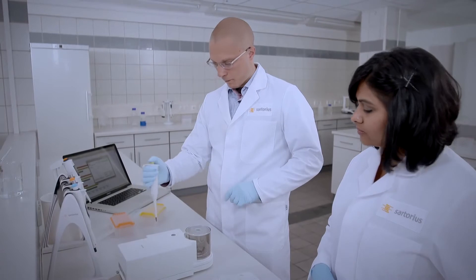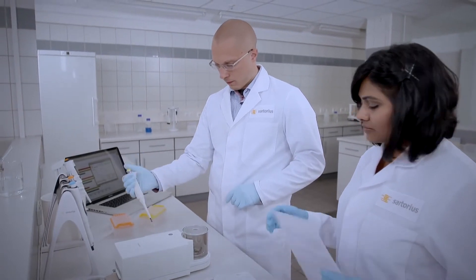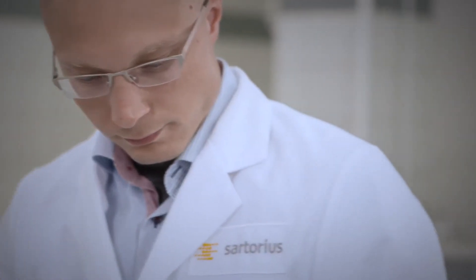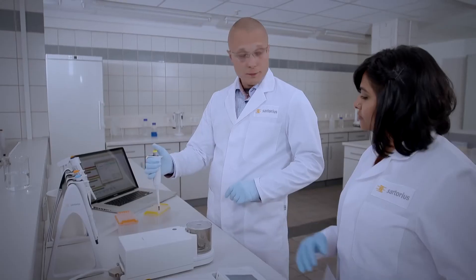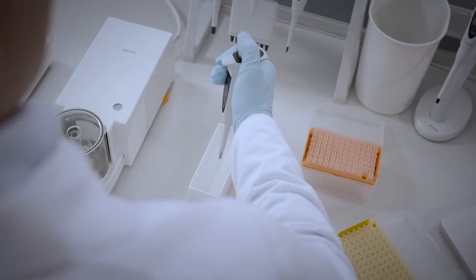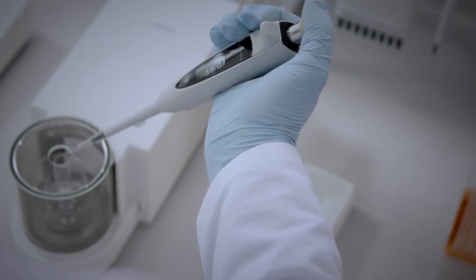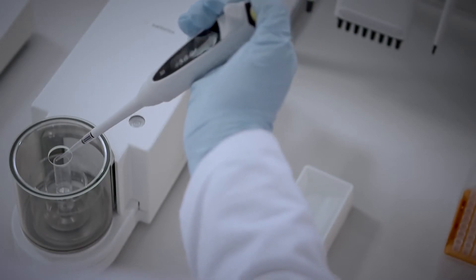Always follow the same procedures to maintain best results for calibration. The most important factors to remember when performing pipette calibration are to pre-wet the pipette, hold it vertically when aspirating liquid, and position it at a 45 degree angle when dispensing into a vessel on a balance.